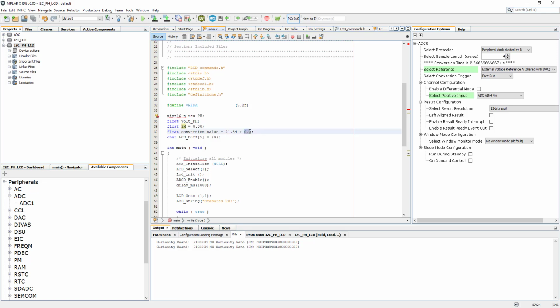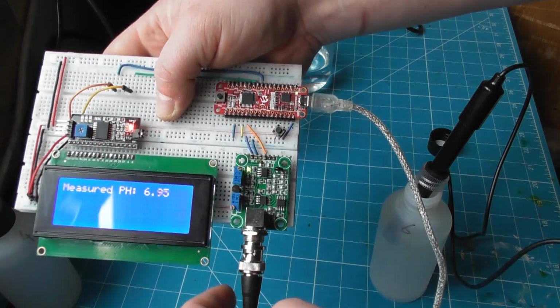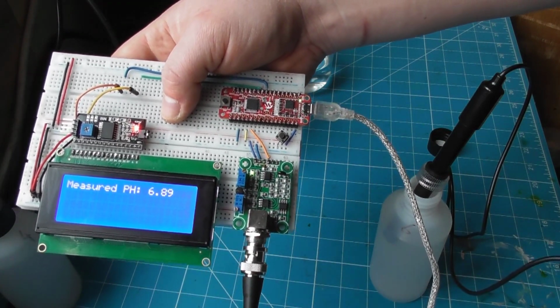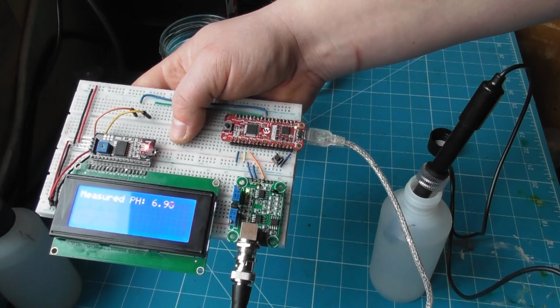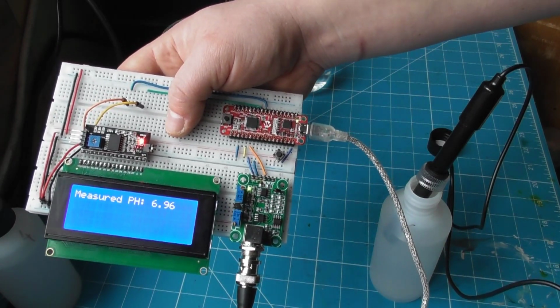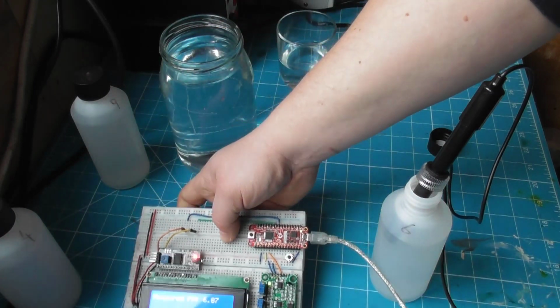In here, if we scroll up, then we see this 0.0. This is our calibration value, as we've said. So now I'm looking to add about 0.28 to the value. This is still quite precise because we're talking about 2 decimal places, and I'm happy with that. Even if there is a fluctuation of 0.1, we still should be happy. So let's go ahead and program that. Let's send this in. So I'm quite happy with how this value came up. Okay, 6.93, 6.9. This is very close to 6.88. I will leave it as it is in here.